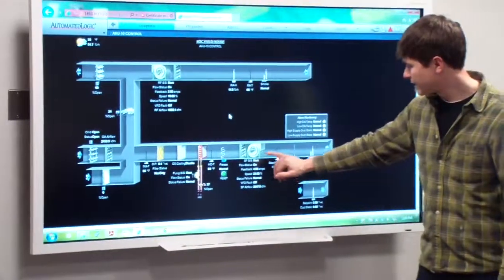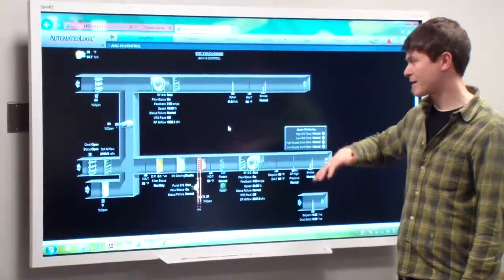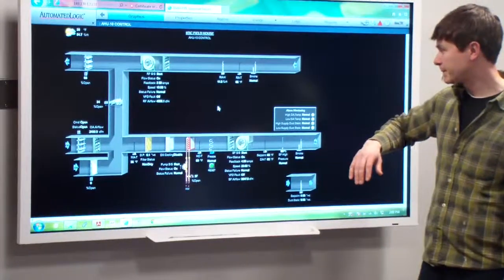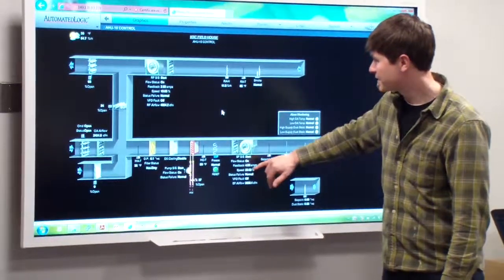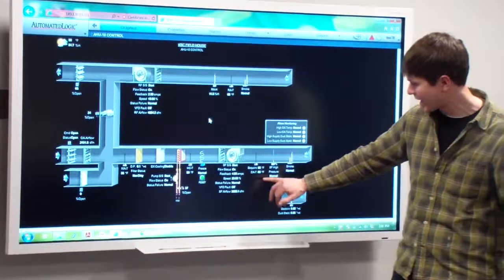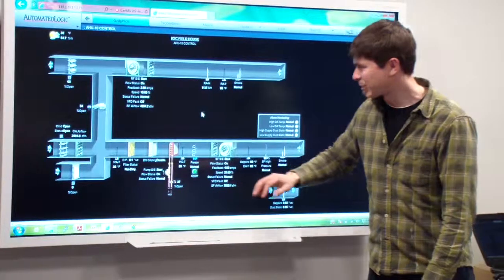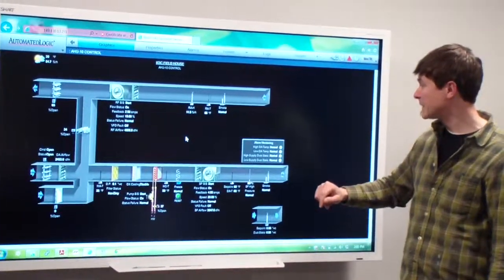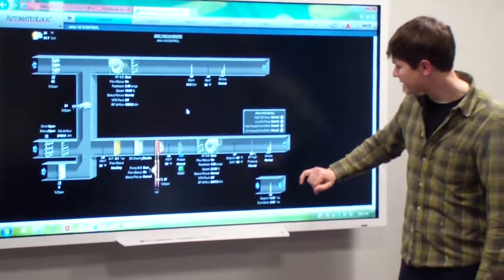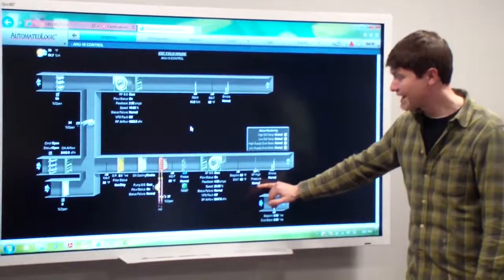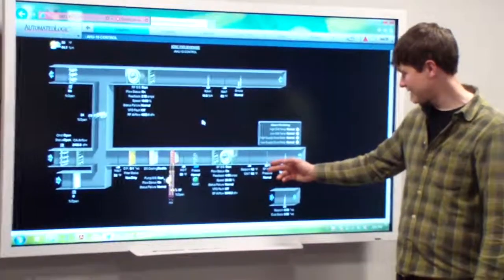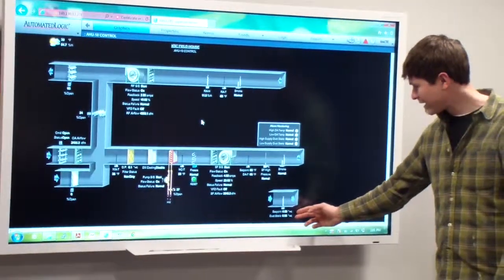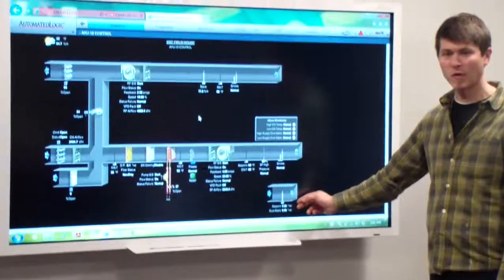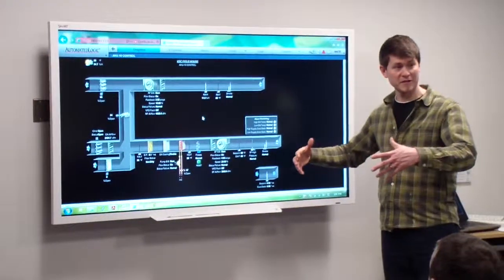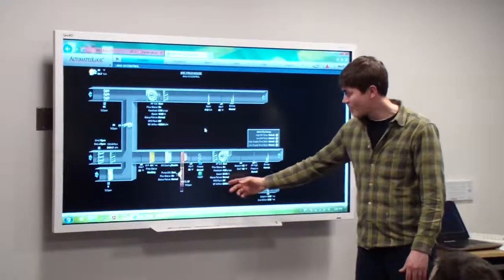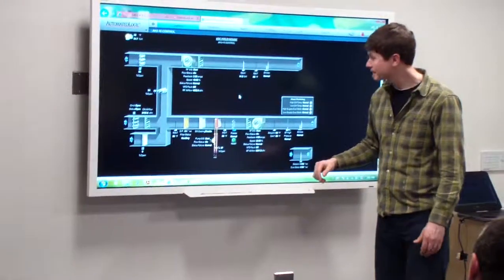Your return fan is tracking your supply fan. Right now, we've got it about 15% shy through programming for what it's seeing in order to maintain a little bit better. You notice we kind of have a negative in the spaces right now, so we're just playing with those numbers in order to balance that out. You've got your duct smokes inside, taking a look. You've got a safety for your supply fan high pressure. Because this says VAV units, you need to have this in place. We're running off of a balancer supplied set point of 0.55 inches water column, which is actually the pressure inside the ductwork. So that determines how much airflow we're bringing into the VAV boxes.